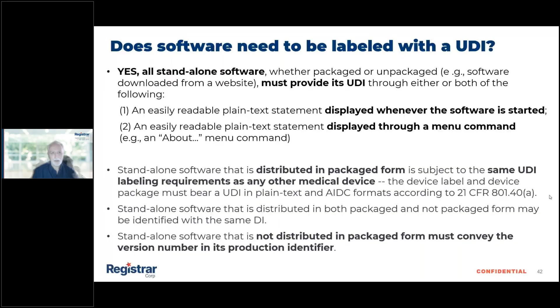As I said, there is a new definition. Standalone software is an older FDA term. Now there is a new term: software intended to be used for one or more medical purposes that performs these purposes without being part of a hardware medical device. That means if you have, for example, an injection pump and you have software that is regulating the pump, that software is part of the hardware. For me, the old term is a little bit clearer here: that is not standalone software. That is a different point.